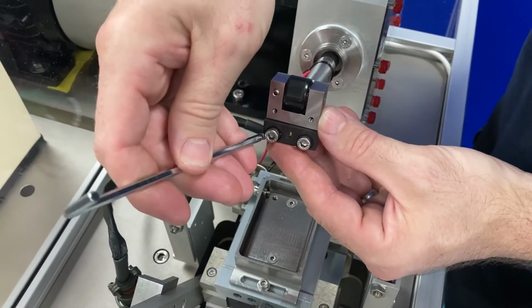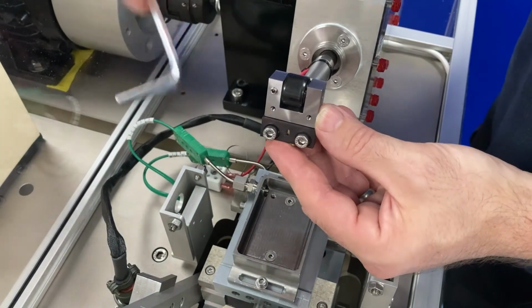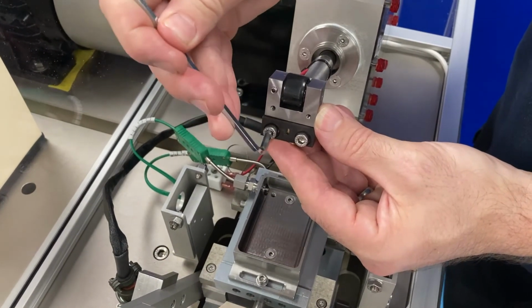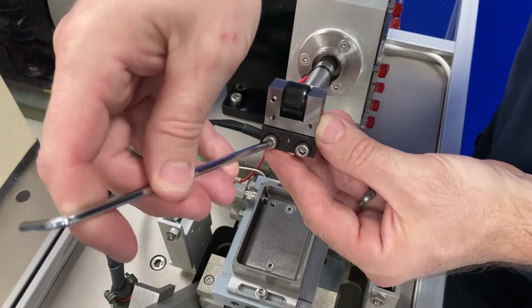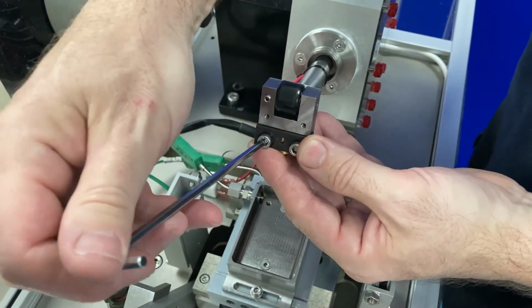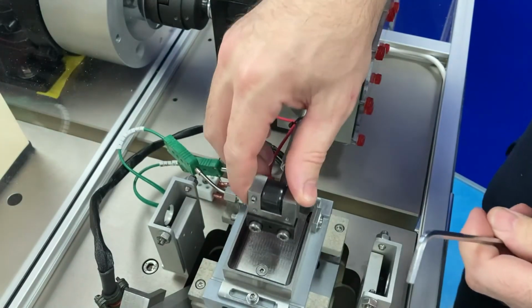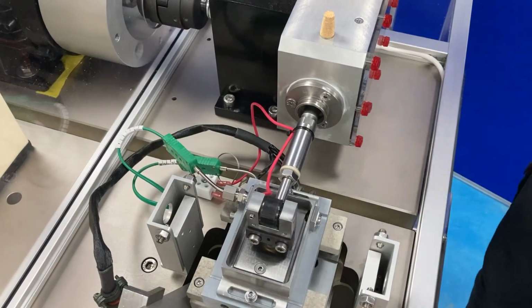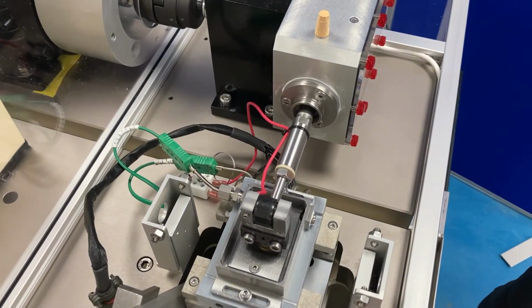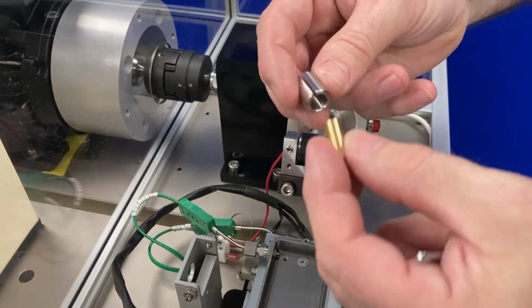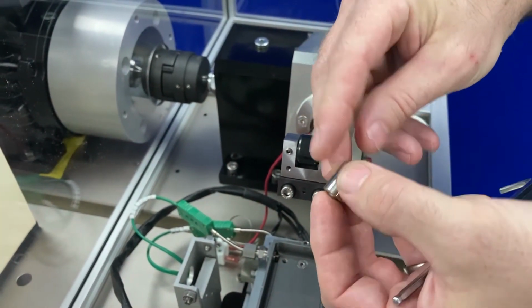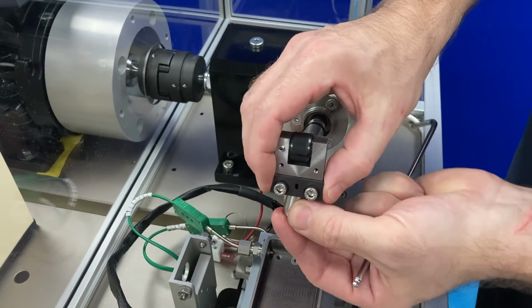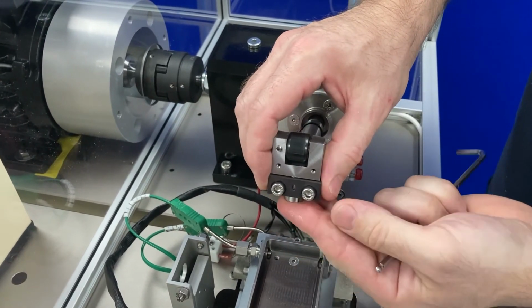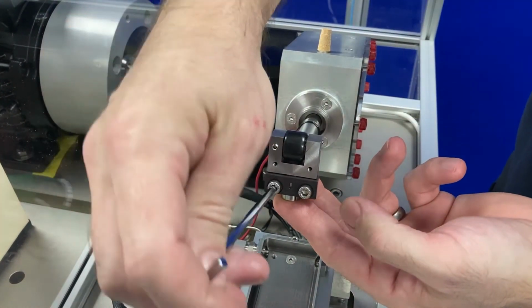It is important that when the machine is running, the cam housing is level. The specimen position in the reciprocating head may need to be adjusted to ensure that this is the case. The 6mm ball specimen is in a smaller diameter tube. To fit this to the reciprocating head, we use an intermediate sleeve.